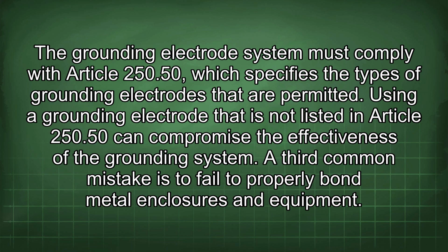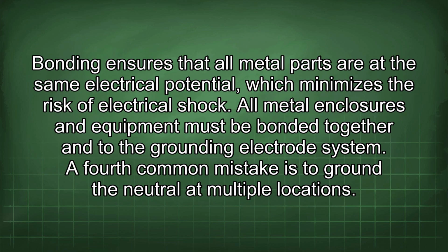A third common mistake is to fail to properly bond metal enclosures and equipment. Bonding ensures that all metal parts are at the same electrical potential, which minimizes the risk of electrical shock. All metal enclosures and equipment must be bonded together and to the grounding electrode system.